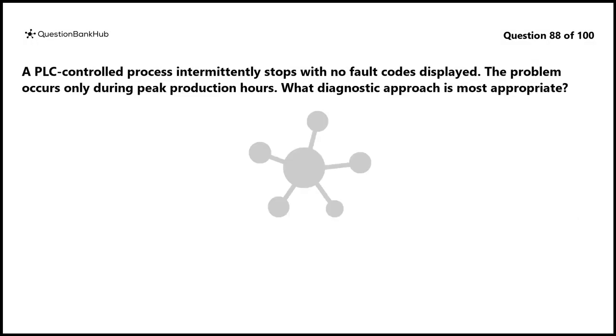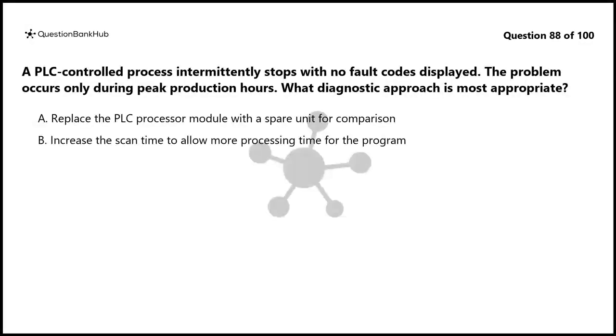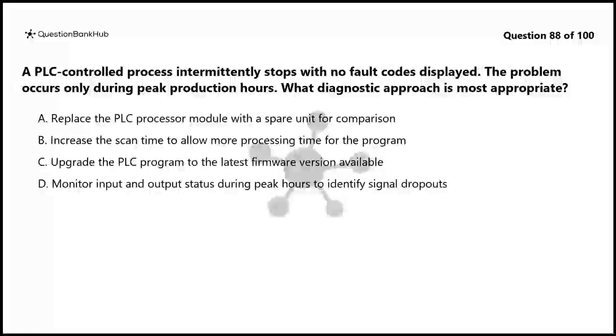Question 88. A PLC-controlled process intermittently stops with no fault codes displayed. The problem occurs only during peak production hours. What diagnostic approach is most appropriate? A. Replace the PLC processor module with a spare unit for comparison. B. Increase the scan time to allow more processing time for the program. C. Upgrade the PLC program to the latest firmware version available. D. Monitor input and output status during peak hours to identify signal dropouts.